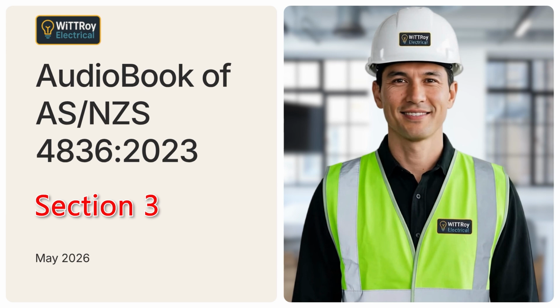Clause 3.3. Testing plug-in electrical equipment. Clause 3.3 explains testing of plug-in electrical equipment. When energized, fault finding or testing is carried out on electrical equipment that plugs into a socket outlet. An isolating transformer or an RCD should be used for protection from electric shock. RCD means residual current device.